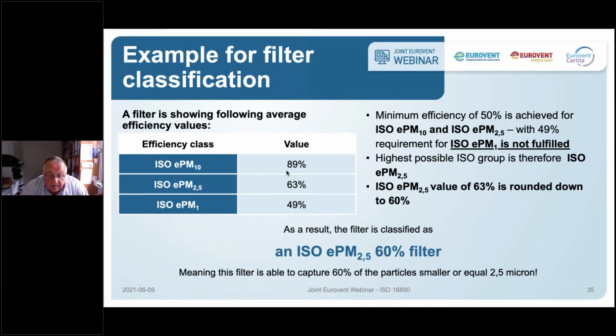So the highest possible ISO group for that filter is ISO ePM2.5. So it has an efficiency for ISO ePM2.5 of 63%, and that's rounded down in 5% steps to the next 5% value, 60%. As a result, that filter will be classified as an ISO ePM2.5 60% filter, and that will be on the label.